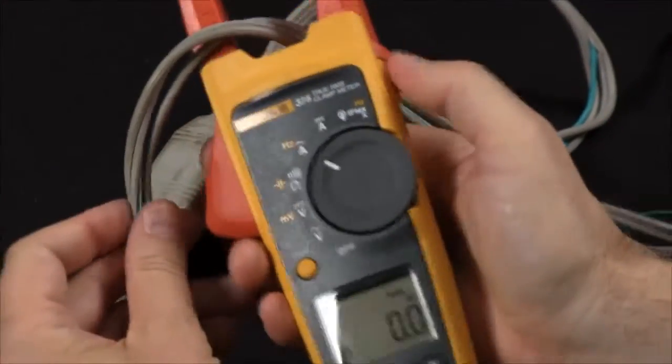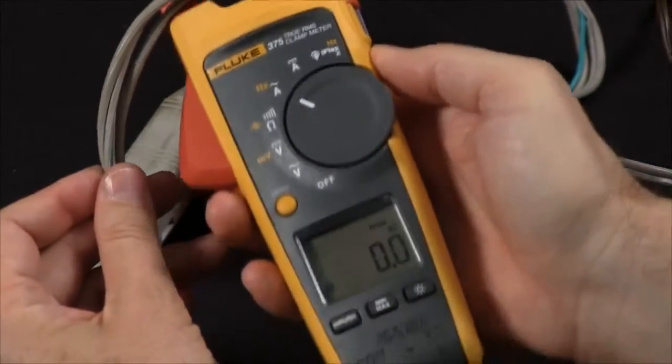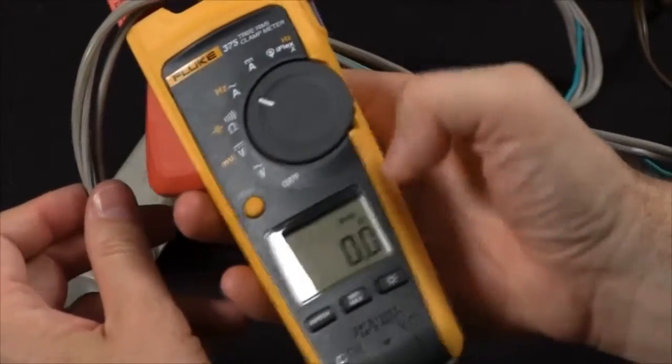A mistake that a lot of people make is trying to measure around the entire cord. You'll see that the flow going through my hot and returning through my neutral is going to cancel out, and we'll see a zero indication on the screen.